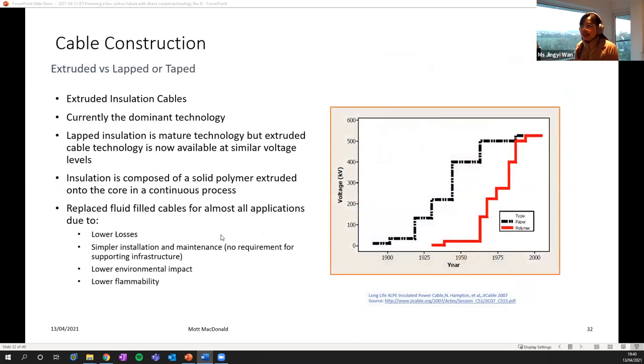Moving to insulation. Extruded insulation cables are currently the dominant technology. Extruded insulation is composed of a solid polymer extruded onto the core of the conductor in a continuous process. It replaces fluid filled cables for almost all applications, namely due to lower losses, simpler installation and maintenance because there is no requirement for supporting infrastructure, lower environmental impact, and lower flammability.